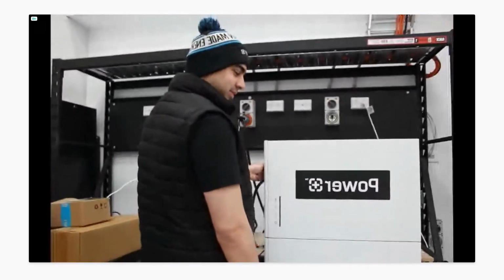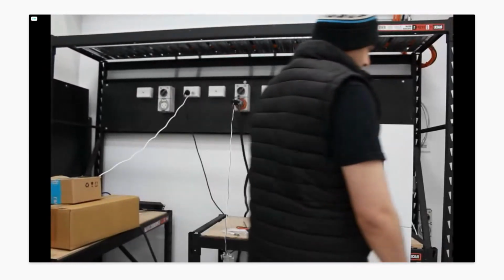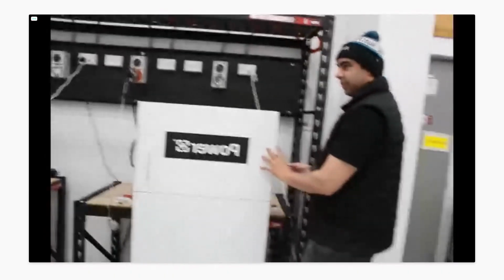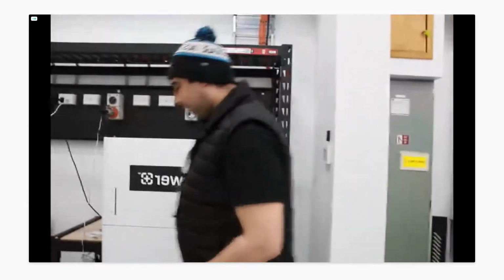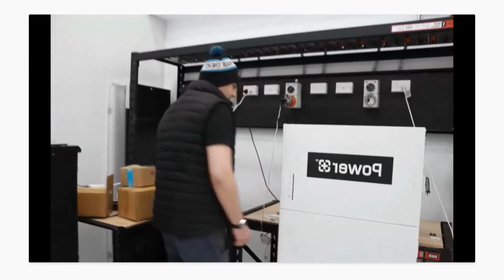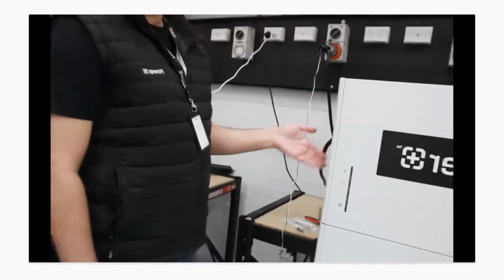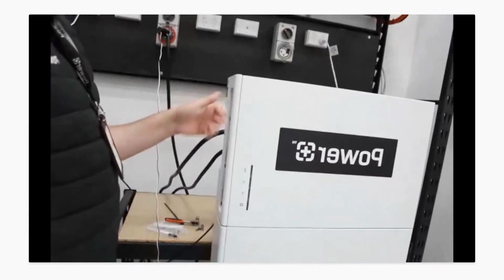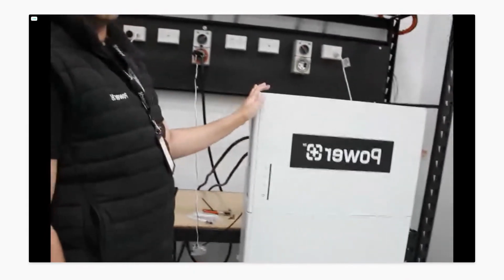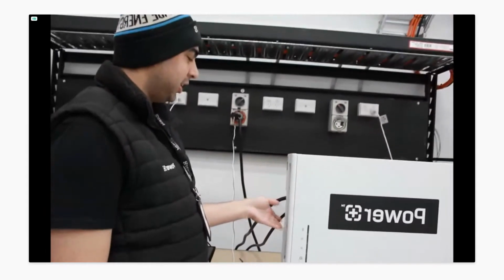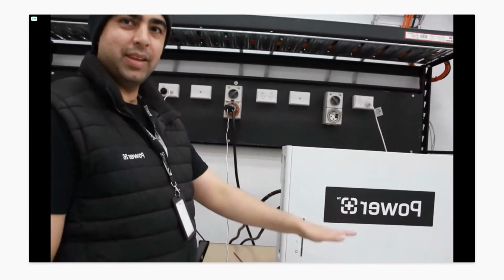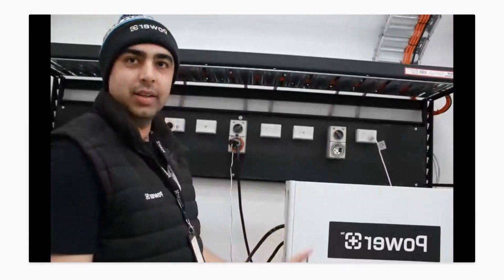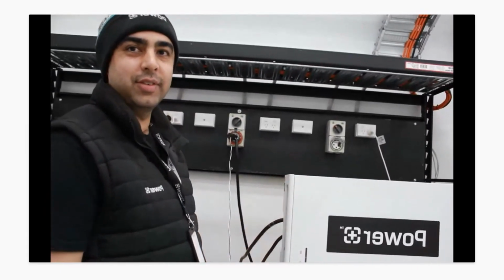You turn the PV breaker on first, then turn on the battery breaker. The order between PV and battery won't matter too much, it's mainly that it's just before the AC breakers. If we close the AC breakers first and do the DC breakers second, you're more likely to get an arc across the DC breakers, because it's a transformerless system. Closing the AC completes a circuit out to somewhere. But if the AC breakers are open, it's got nowhere to go, so you're less likely to have arcing on the DC switch.